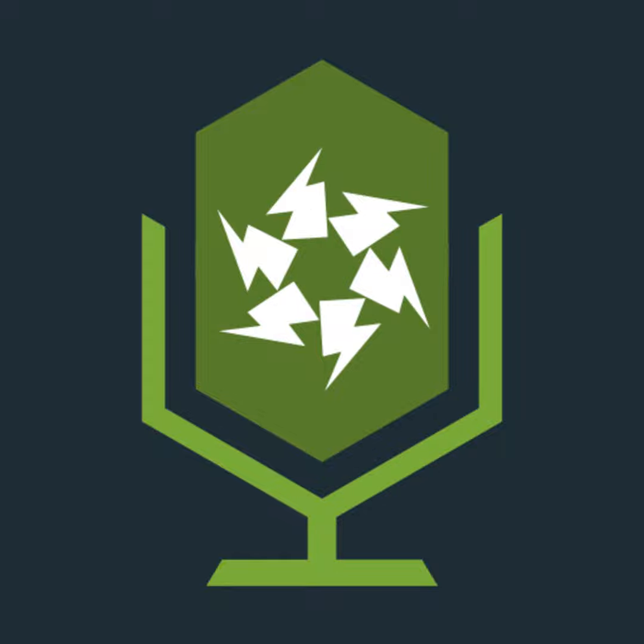To add a little bit to this, there's a lot of development needed in testing, because a lot of people don't know how to test these kinds of systems. Technically, with this kind of system you want to do an earth fault loop impedance, external Ze, twice, because you have two of them, and a Zs within the system twice, L1 to earth and L2 to earth. Whilst they would technically be the same, you should be recording and testing them suitably.